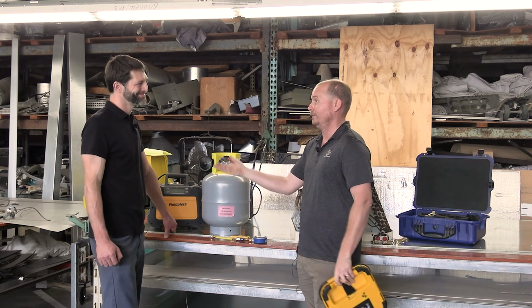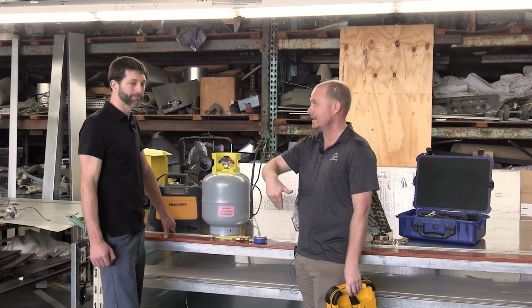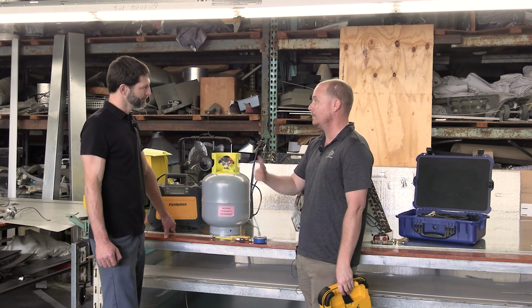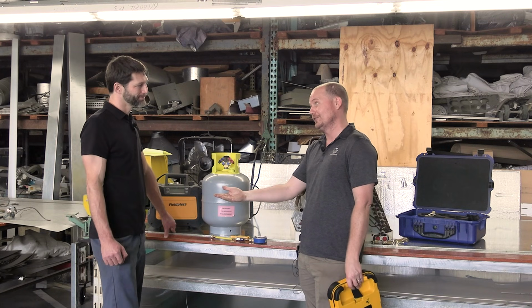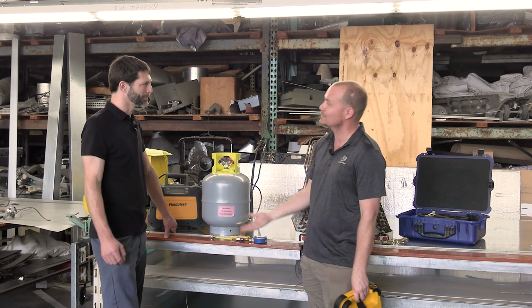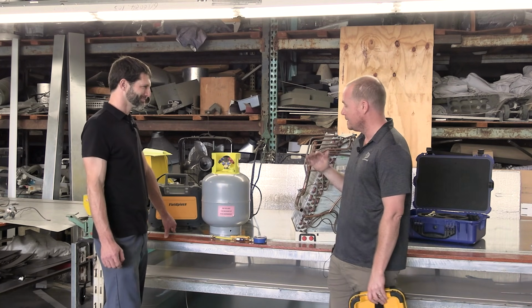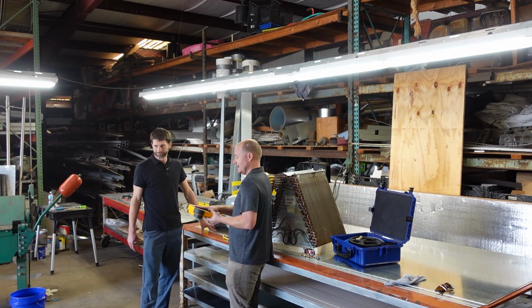Well, now you better look for other leaks in the system before you go ahead and slap that new compressor in. Or if it has double the charge it's supposed to have, now you want to look to see if you have an airflow problem, because somebody was probably compensating for something else by adding too much charge. So this scale is really key.